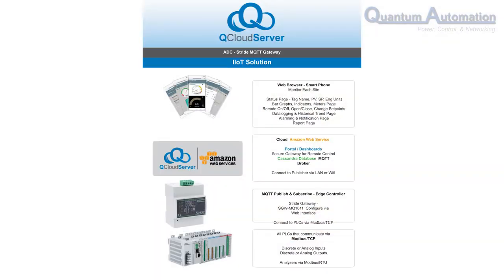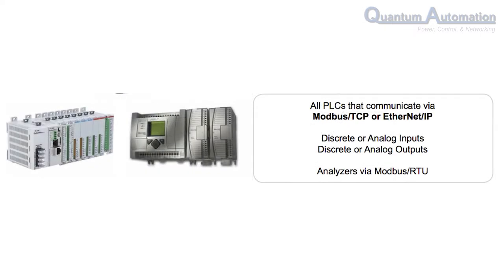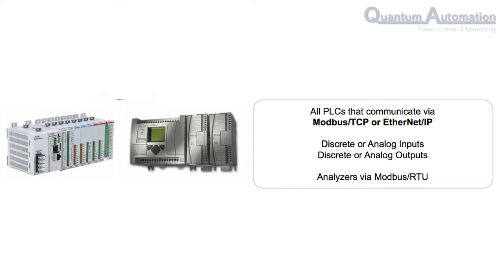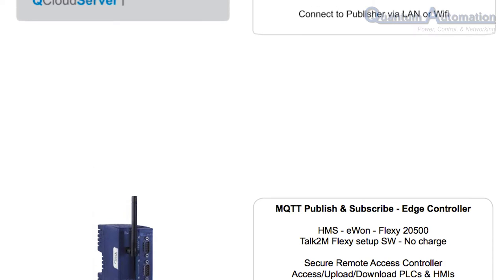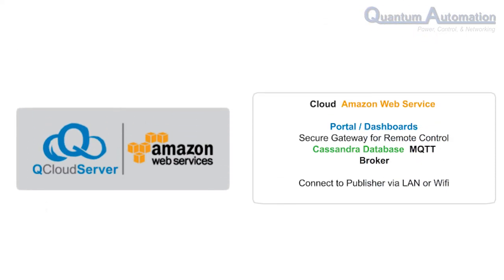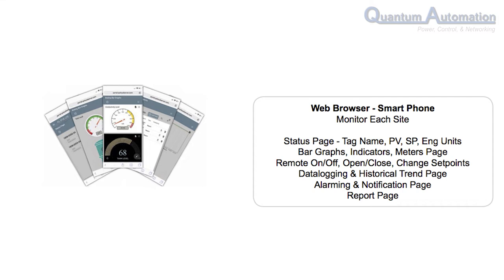So just how do we do this? As we look at this IIoT data sheet with a Flexy Edge controller, let's start at the bottom where the sensors come into the PLC and note the protocols that we accept. We then introduce an Edge controller, which is an MQTT gateway to publish and subscribe information to and from an MQTT broker server in Amazon Web Services or Azure. The MQTT broker sends the data to another server called the Portal to generate dashboards, and to the Cassandra database server for logging purposes. The dashboard looks and feels like an HMI, consisting of a status page, an indicator page, a control page, a trend page, an alarm page, and a report page.